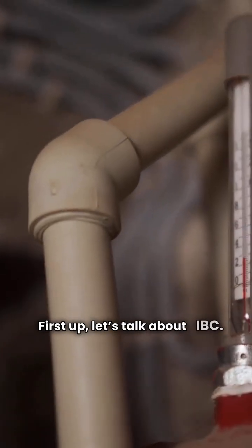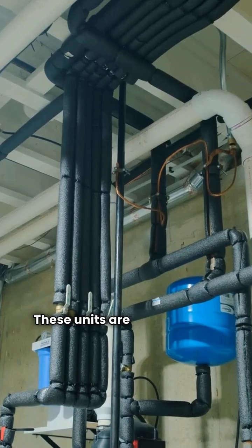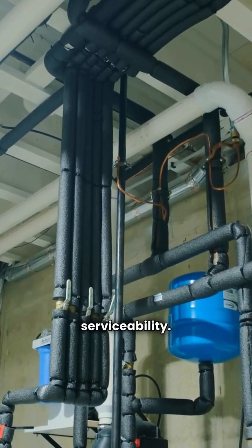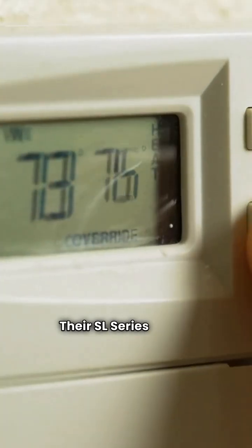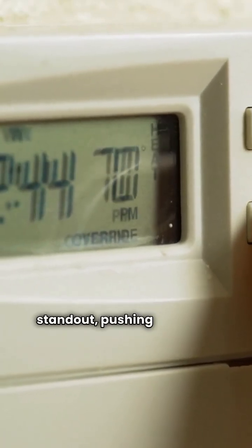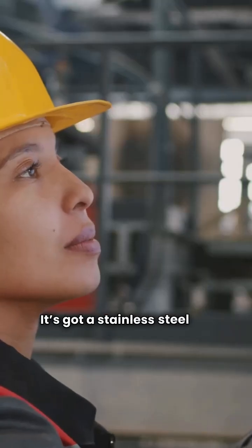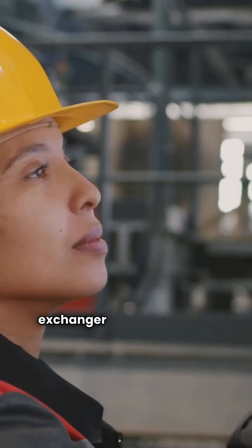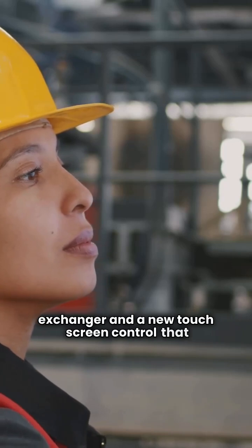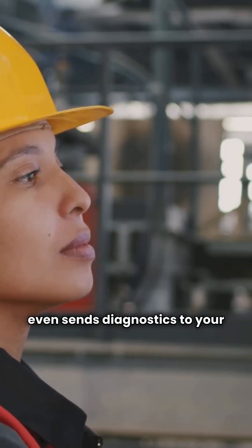First up, let's talk about IBC. These units are built with one thing in mind, serviceability. Their SL Series G3 is a standout, pushing 96% AFUE efficiency. It's got a stainless steel fire tube heat exchanger and a new touchscreen control that even sends diagnostics to your phone.